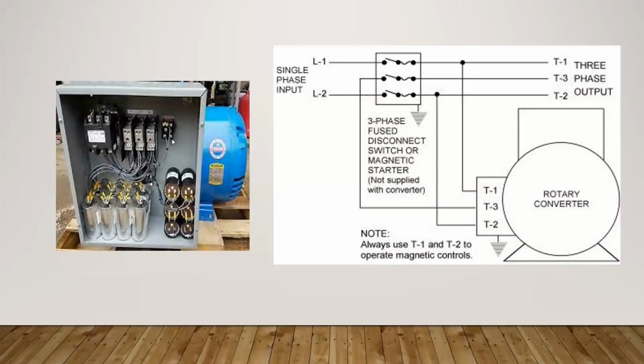And then they have a time delay. Sometimes they use time delay, sometimes they use voltage sensors. But what they're doing is basically powering up from the line power here, line 1, line 2, getting the rotary converter running by putting in start capacitors and then run capacitors. So it's literally a single phase device that gets that rotary turning. Then after it's up to speed, these start capacitors drop out, and then it provides three-phase power.